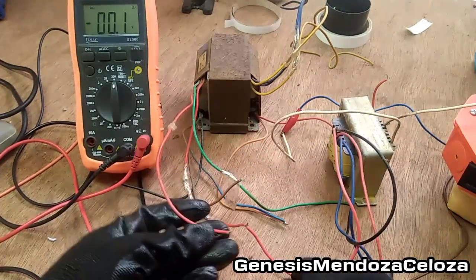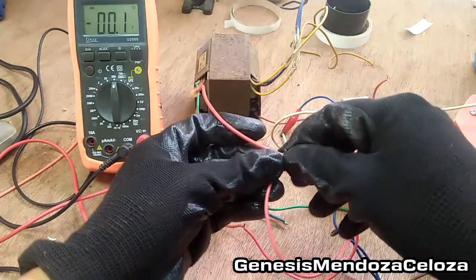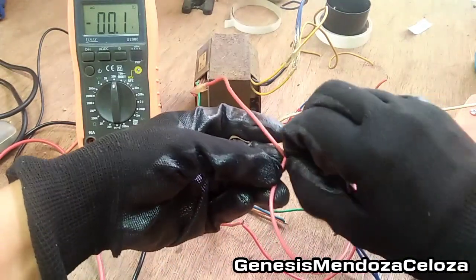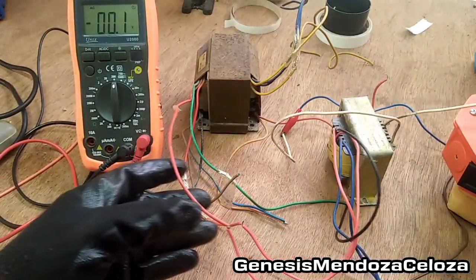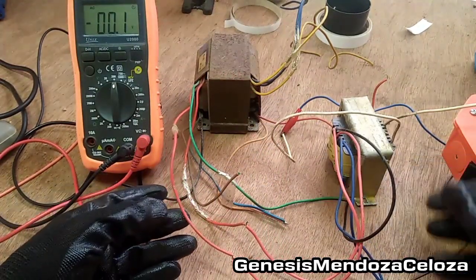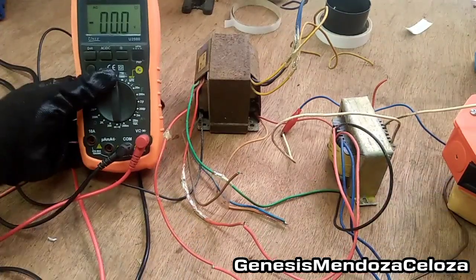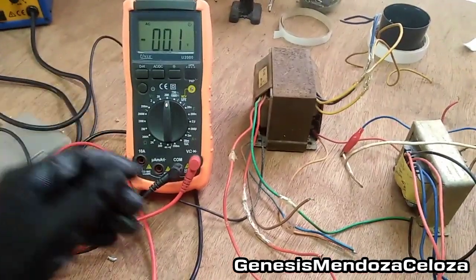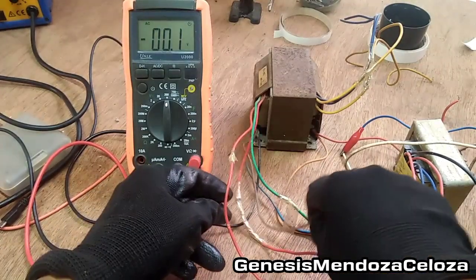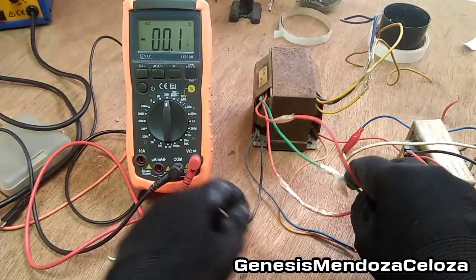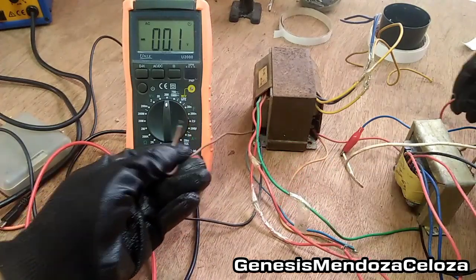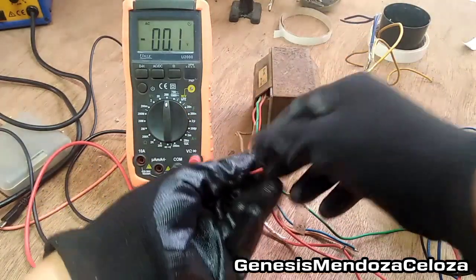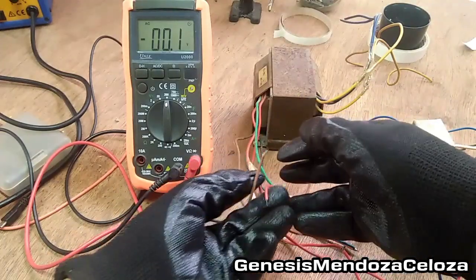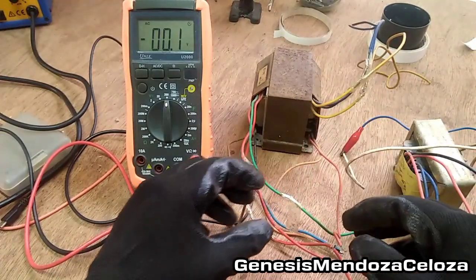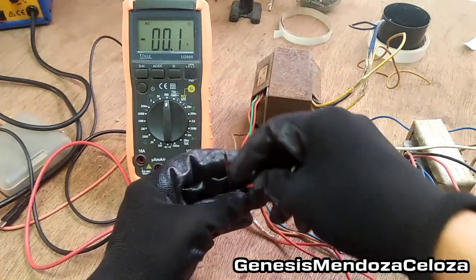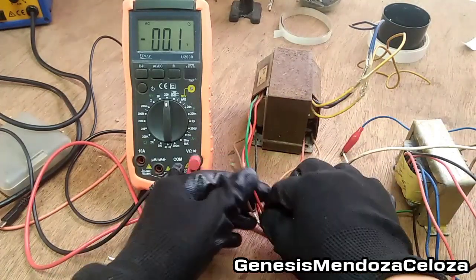Typical homemade isolation transformer. For supercritical applications like in hospitals where every microamp of leakage counts, special isolation transformers are available, no doubt at equally super costs, which have shielding between the primary and secondary to minimize the interwinding capacitance and inductance as well. This should not really be necessary for general servicing.